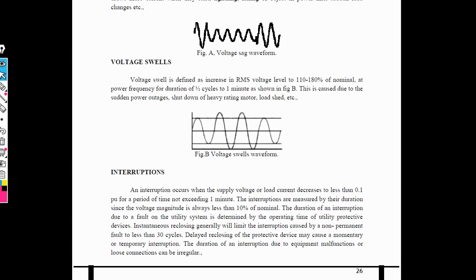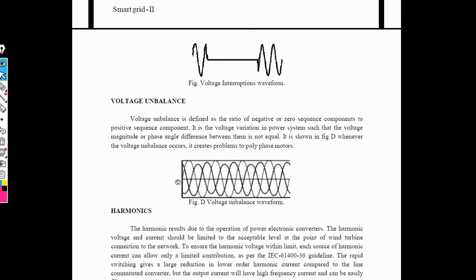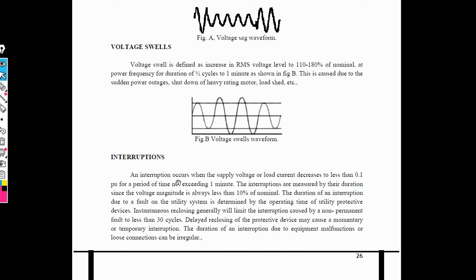Then the next point is interruption. That means interruption also depends on load. When supply voltage is applied, then load current flows from the input side to the output side. Then voltage is unbalanced at that instant. Small, large and medium interruptions occur. That means we also have to measure the duration of the voltage magnitude. When the voltage magnitude is less than 10% of nominal voltage, this is called interruption of voltage.